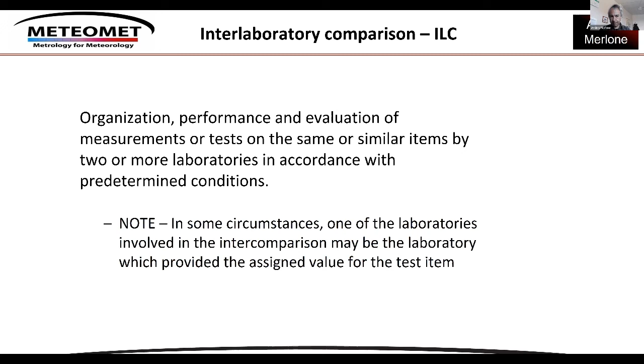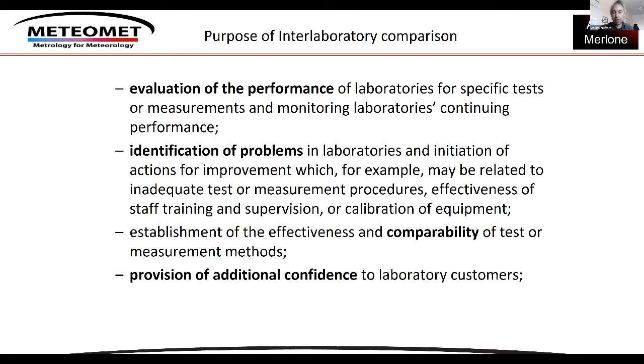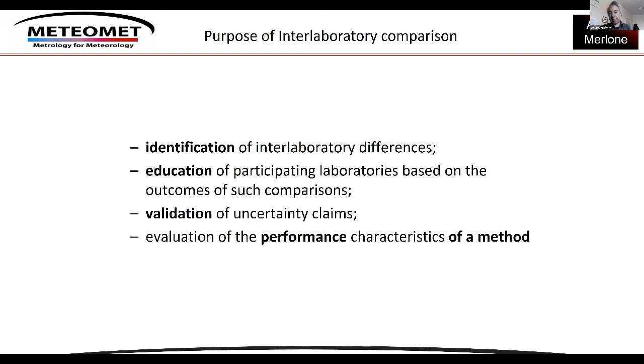It allows us to evaluate the performance of the laboratory. Again, translated to instruments, we can evaluate the performance of the instrument for specific tests. We can identify problems which maybe you couldn't if you just bought an instrument, put it there and trusted the instrument. And this is also true for a lab. Maybe I didn't know, but I have such ground noise that I'm not able to get the required sensitivity of my multimeter to detect some amount. But I realize this only when another person from another lab comes and says, my instrument was working properly there. It establishes comparability and it gives confidence to the instrument or to the laboratory. We can identify differences, again, translated to instruments. We can train people to use the instrument or to work in the lab, and evaluate the performance and characteristics of the methods and of the uncertainty.